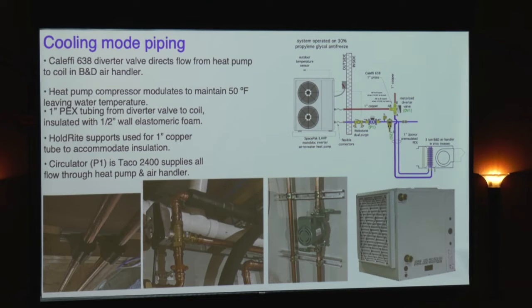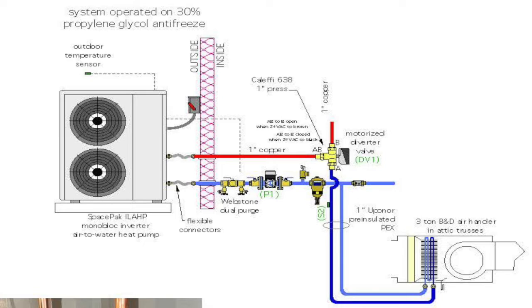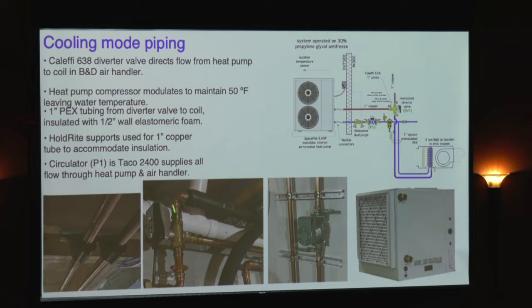Okay, cooling mode. I mentioned here's the valve. Flow comes, this would be chilled fluid now coming in from the heat pump. It hits that valve. This is 1-inch PEX with 1/2-inch elastomeric foam insulation, all glued together, taped up. You've got to do the insulation right with chilled water. If air can get to your chilled water piping, I guarantee you're going to have condensation, and it's going to drip somewhere. Maybe it's on the basement floor, maybe it's above a drywall ceiling, and it's going to get your attention as a callback very quickly. So chilled water cooling is very viable today in residential, but be careful with the insulation. If air gets to anything with chilled water in it, it's going to cause corrosion. Okay. You can see some of the insulation here wasn't finished yet.